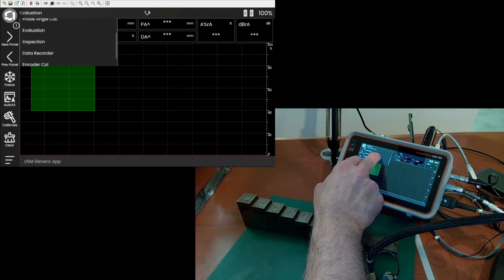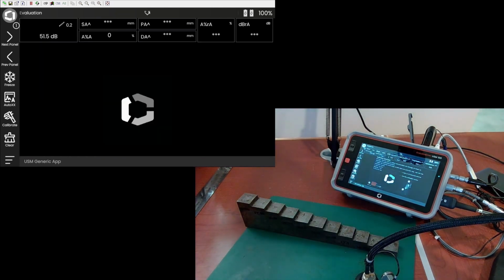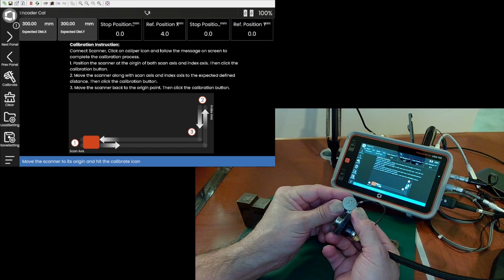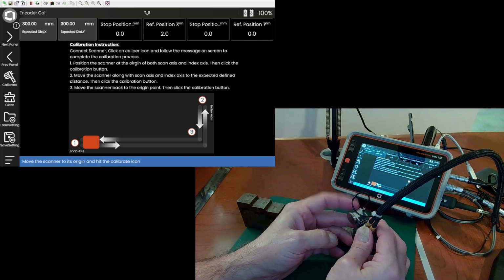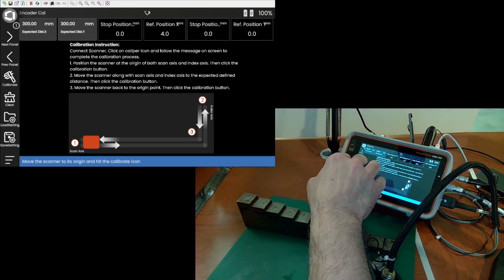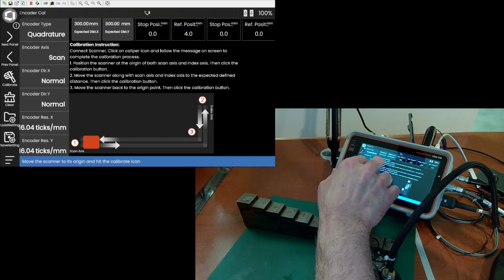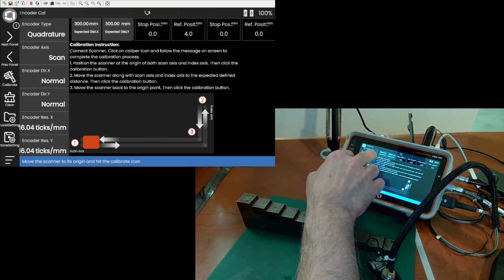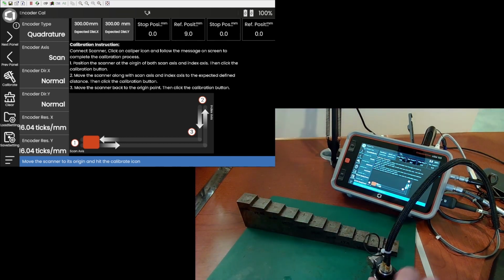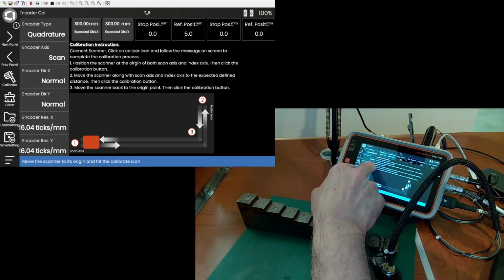So let's just take a look at encoder calibration. Again, I have a little magnetic wheel attached to the back of the probe holder. So let's swipe out our sidebar menu and take a look at a few things. We're going to do a quadrature encoder. This is only a 1-axis encoder. And when we get to our scanning tank, we will look at doing both the X and Y axis. We refer to the X axis in the Mentor instruments as the scan axis, and the Y axis is the index axis. Okay, so we're just going to calibrate the scan axis.